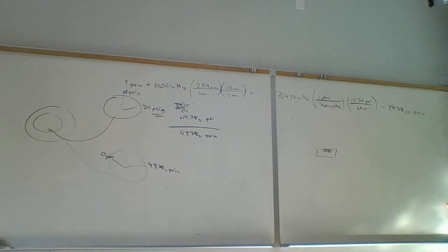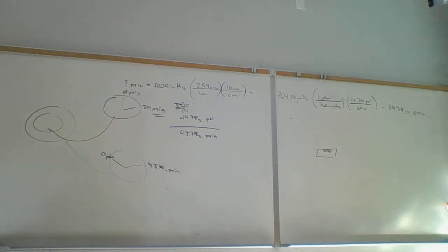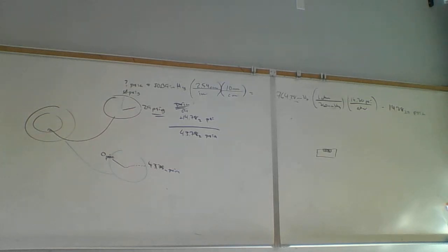If we just twist it, because here we have the absolute 0, here we have the arbitrary 0. So we're going to just take the faceplate and twist the 0 so that it matches the absolute 0. Then what is the pressure reading? The difference between the two gauges is very simple. The difference between the two gauges is where they print the zero. That's the only difference.